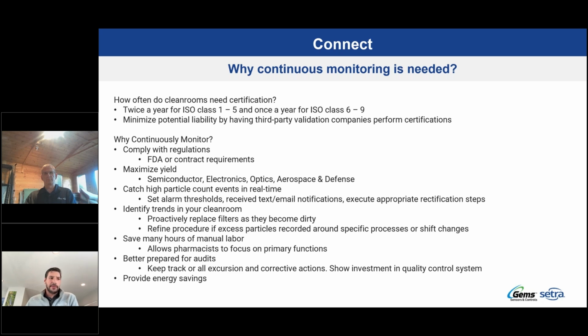I mentioned you can obviously catch your high particle count events in real time. You can identify trends within your clean room. So this is big as well. So, if your filters are getting dirty over time, you'll be able to see that proactively by your particle count readings kind of inch up week over week. Similarly, if you had any issues with, say, your gowning process not going properly, and every time there's a shift change, there's a big excess in particles that flood your clean room, you'd be able to capture those types of events by having a mounted particle counter regularly sample, where, if you just had someone go in once a week or once a day to sample, you might not capture events like that. So there are some benefits.